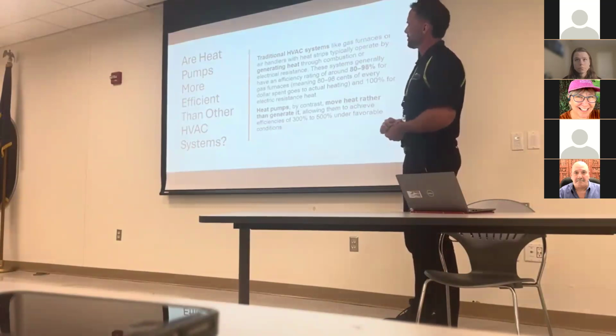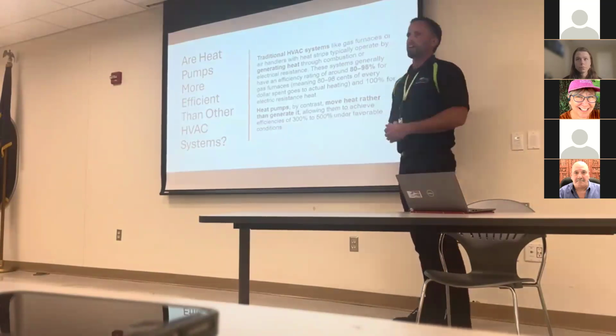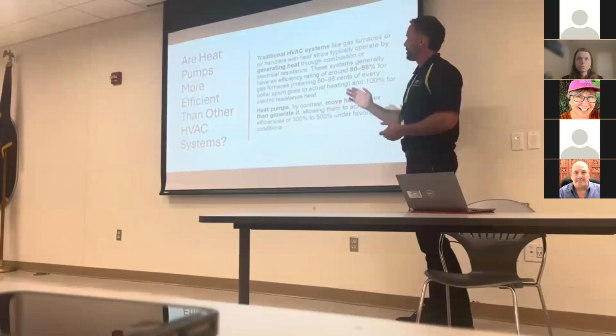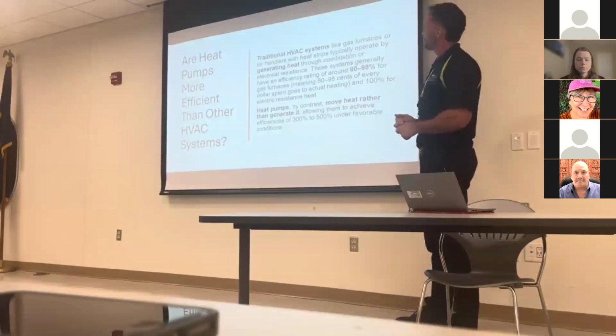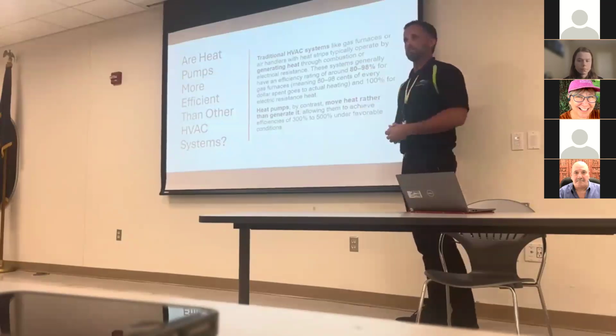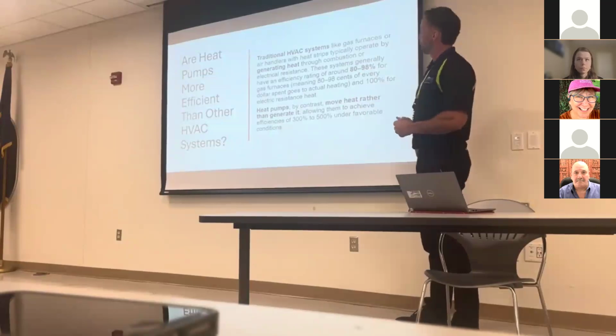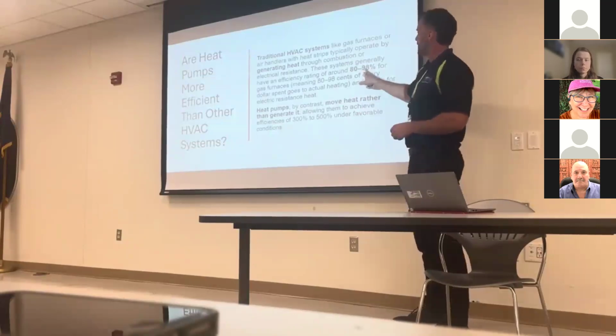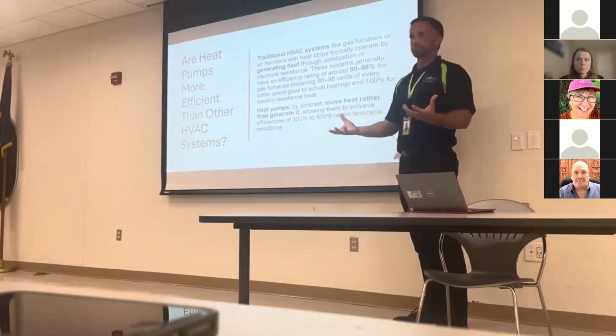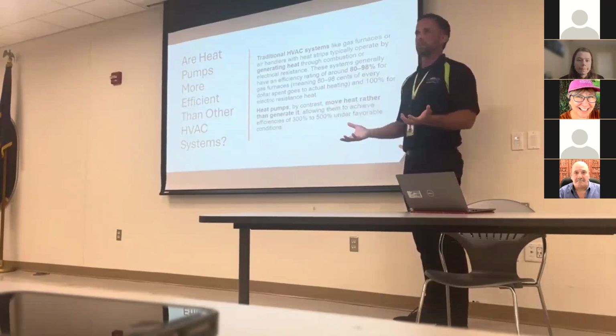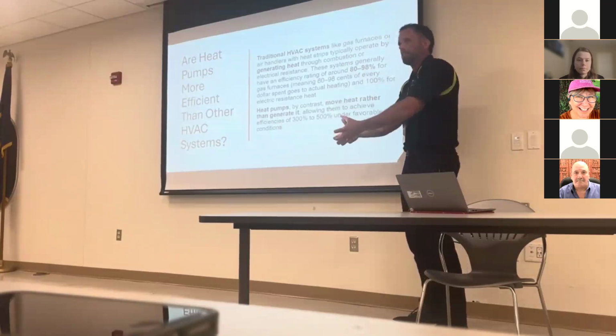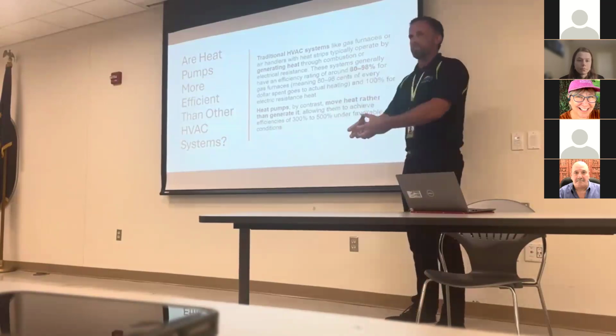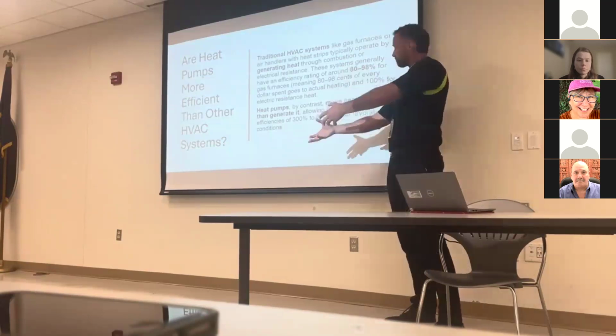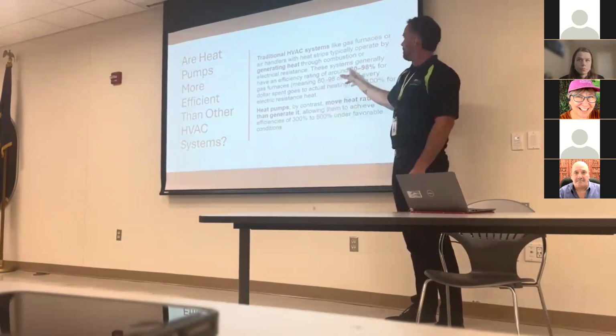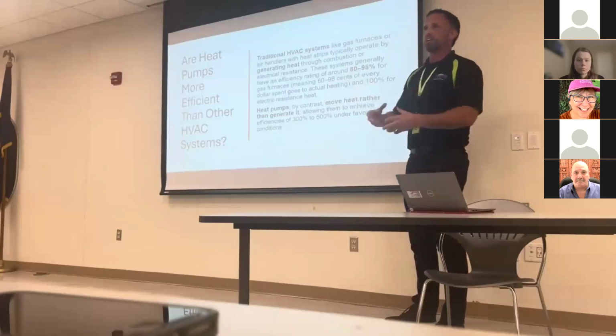So are heat pumps more efficient than other HVAC systems? So you kind of got to look at a few different factors, but traditional HVAC systems like gas furnaces or air handlers with heat strips typically operate by generating heat through combustion, like a gas furnace is combustion. These systems generally have an efficiency rating of around 80 to 98% for gas furnaces. So on a gas furnace, there's always some heat that's wasted. So we'll start a fire in the furnace, and 80% of that, up to 98% of the heat that's produced, will go into the house. And then there's 20% to 2%, somewhere in that range, of heat that's wasted.